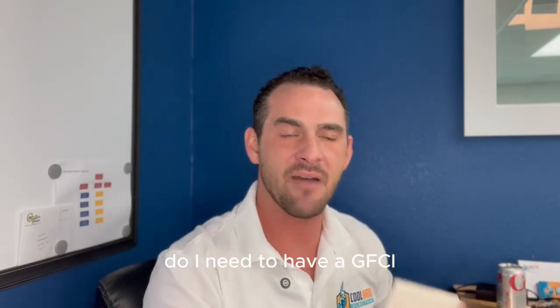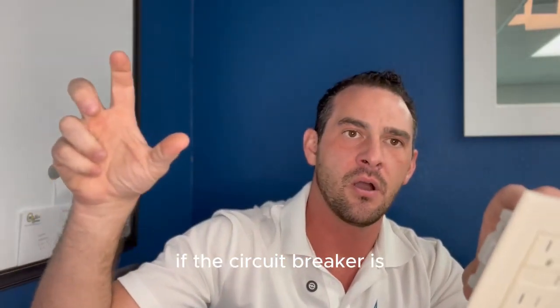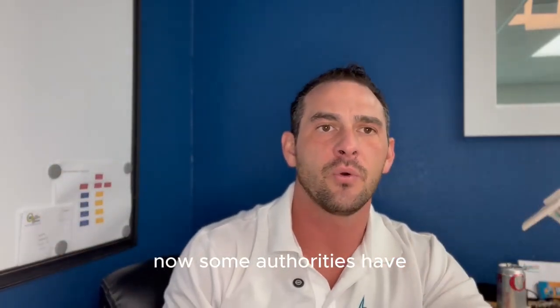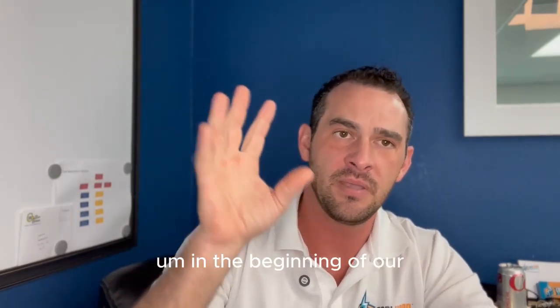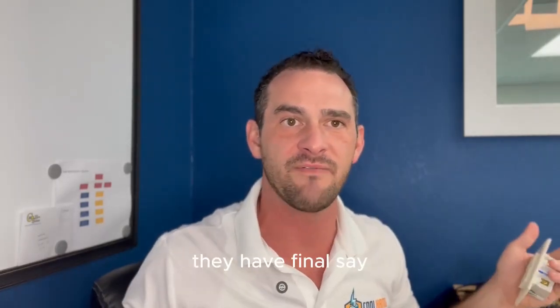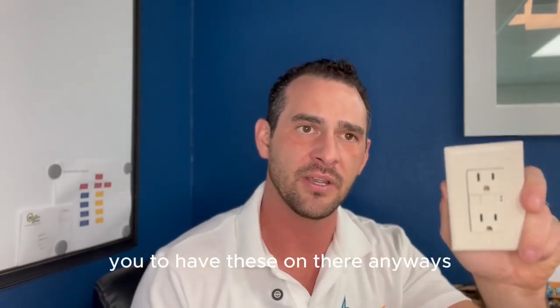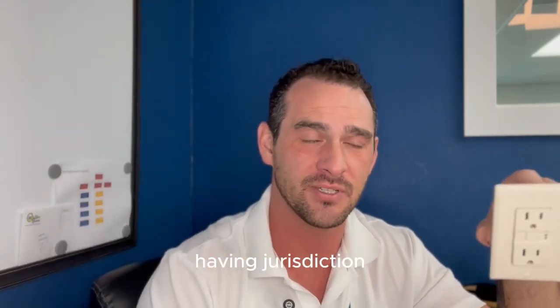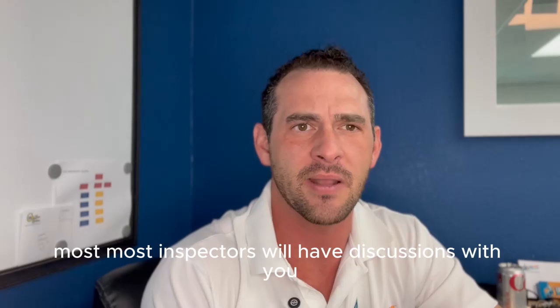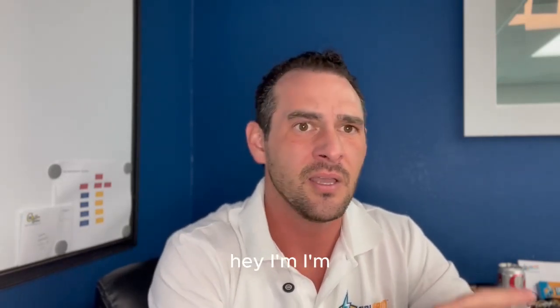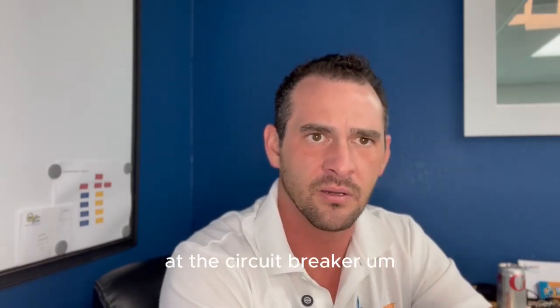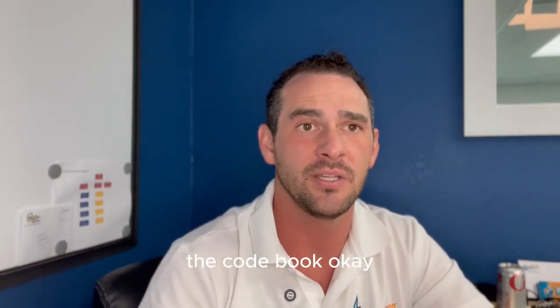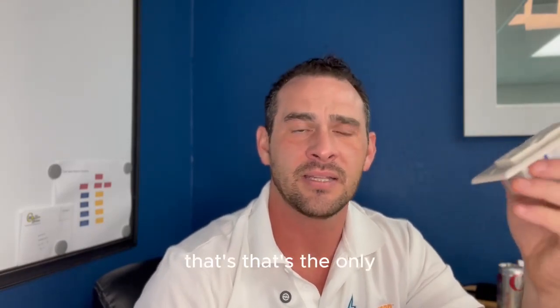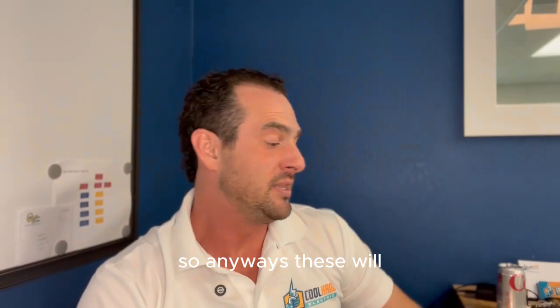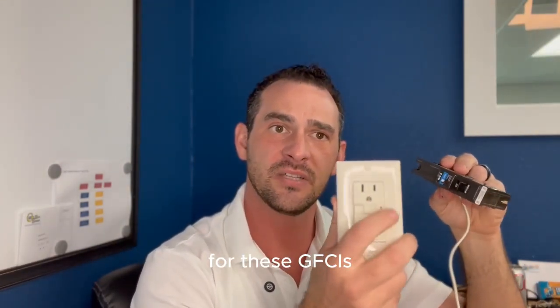A lot of people will ask, do I need to have a GFCI if the circuit breaker is ground fault as well? The answer is no, you don't have to. Now, some authorities having jurisdiction, which is just the term for the local city, in the beginning of our electrical code book, the authority having jurisdiction, they have final say. So if they say, hey, I want you to have these on there anyways, then you got to do it. And then technically it's code because they're authority having jurisdiction. But you could discuss it with them. Most inspectors will have discussions with you as long as you're not rude, and you can say, hey, I'm GFCI protecting the circuit at the circuit breaker. Why do you want another GFCI as well? And they may have a good reason why they want it, but it's not going to be out of the code book. Okay, it just needs to have GFCI protection, whether it's on the circuit breaker or the outlet. That's the only standard. So, anyways, these will eliminate the need for these GFCIs, which is kind of cool.